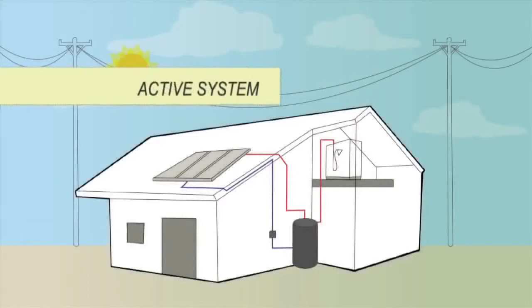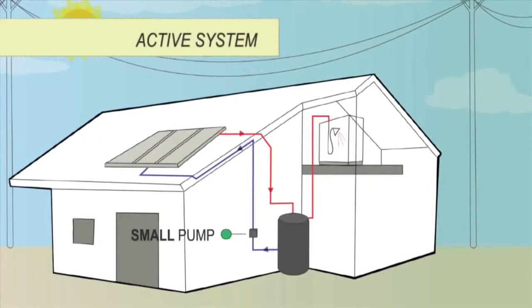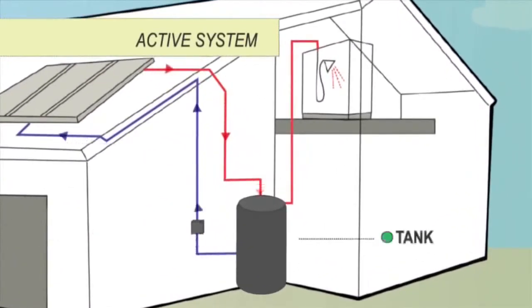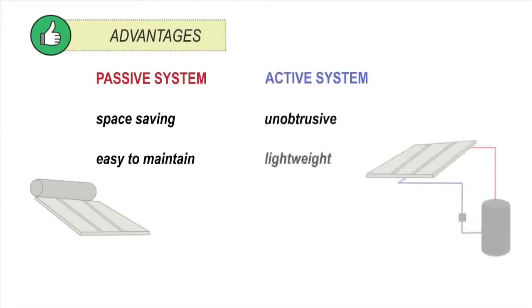Active systems use a small pump to move water between the collectors and the tank. The location of the tank can be within the roof or on the ground. Each type of system has advantages. A passive system is space saving and easy to maintain with no moving parts. An active system is unobtrusive, lightweight, can use an existing tank, and the tank can be located closer to where hot water is used, reducing heating loss in pipes. But the pump uses some energy.